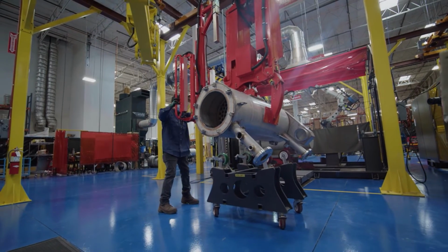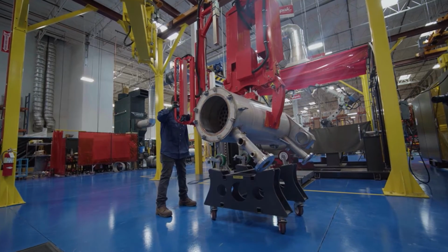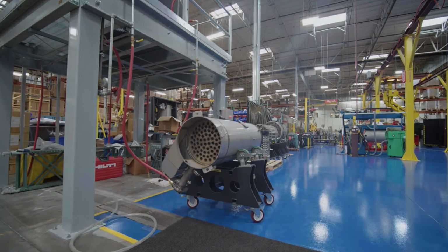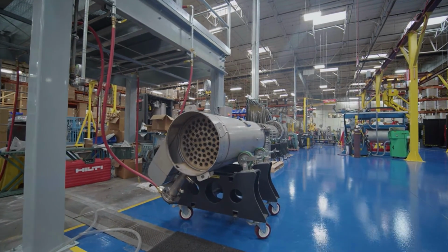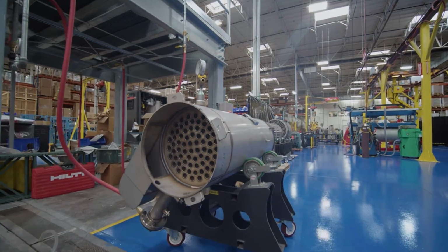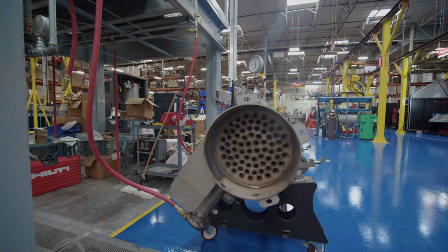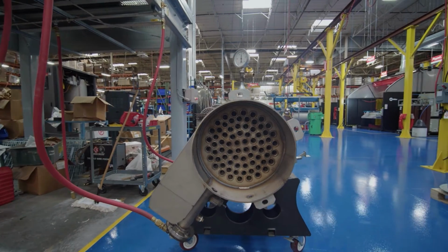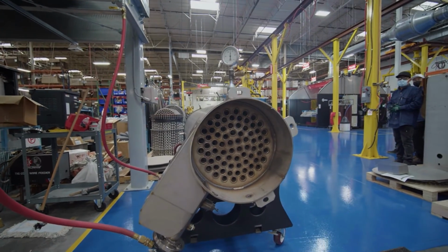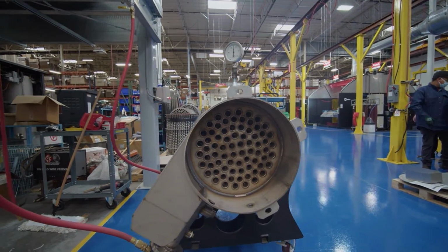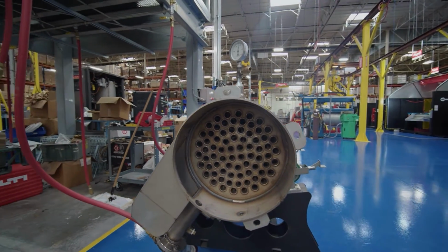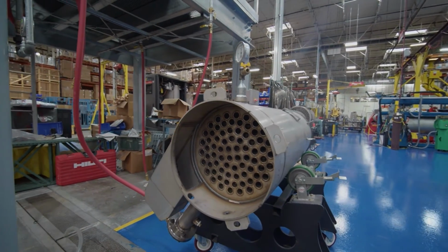An ASME inspector reviews and validates raw materials and subassemblies of the heat exchanger for compliance with ASME codes and Raypak quality control requirements. The heat exchanger is then sent to the hydrotest station, where it is subjected to a hydrostatic test pressure of 240 psi for compliance with ASME pressure vessel code before being placed inside the unit.